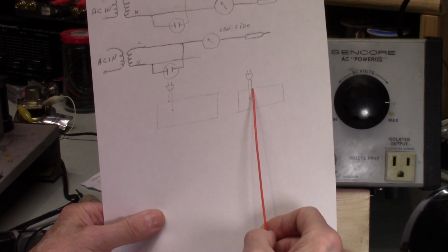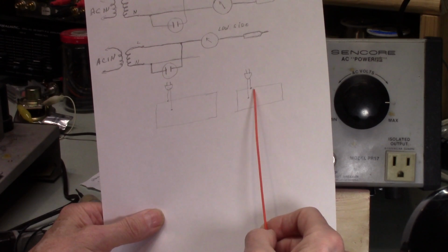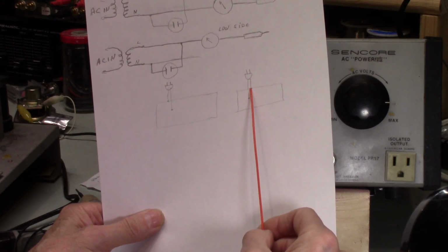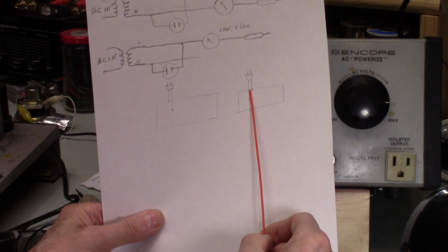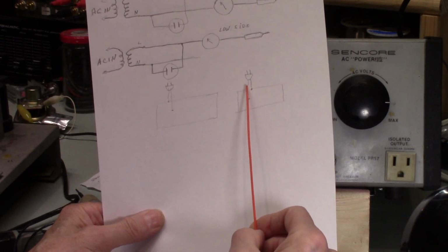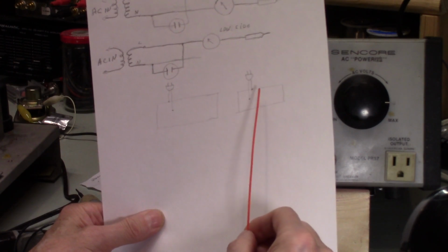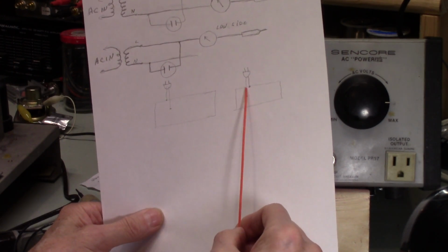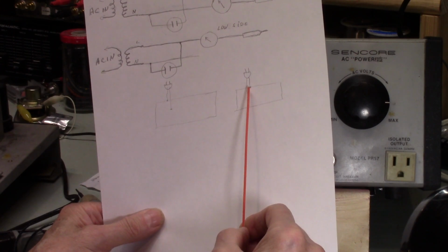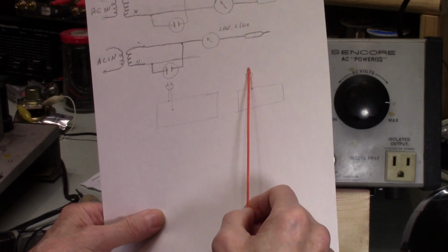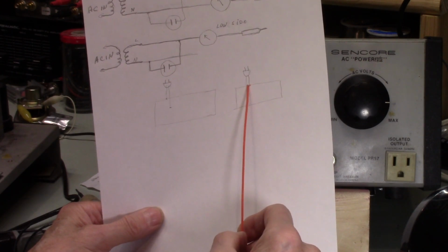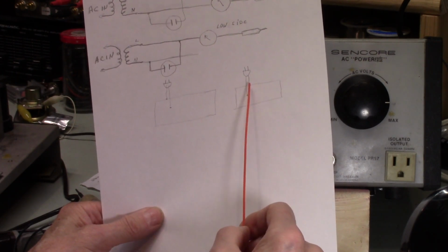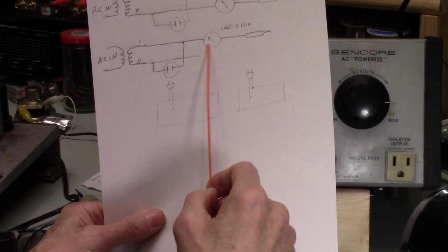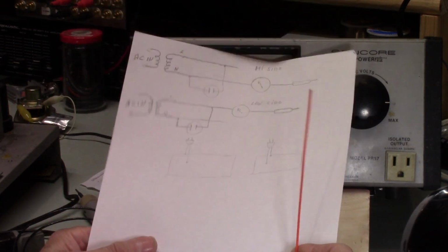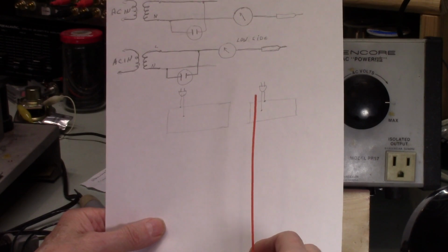In some cases there's a capacitor between this leg of the power lead, which works to reduce the current. So if you have the appropriate size capacitor between the chassis and here, your meter reading will be lower. I hope that makes sense. This is your AC, and this is the isolation transformer in this setup.